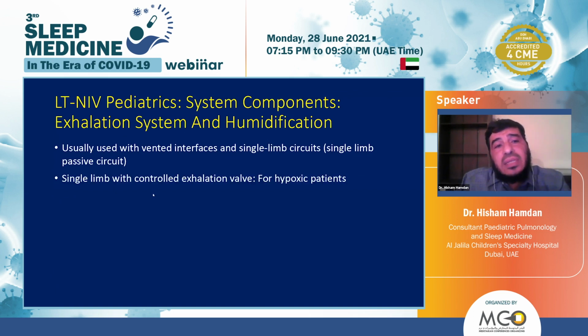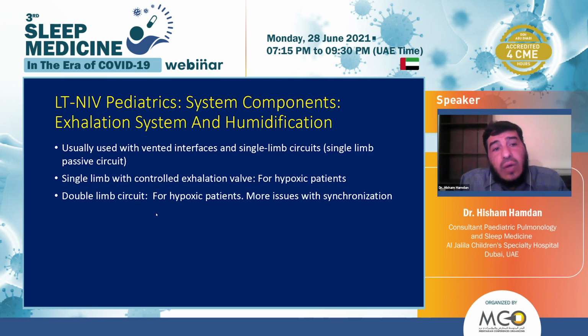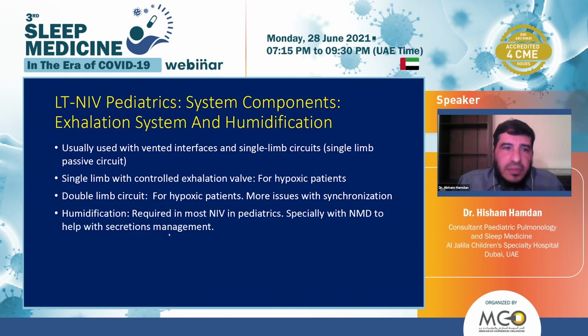The second option is single limb with controlled exhalation valve. So you have one limb, meaning one tube going from the ventilator to the mask, but then you have an exhalation valve that is actively controlled by the ventilator mechanism. And then you have the double limb circuit, which is the most advanced, in which you can control inspiration and expiration. You can see two pipes from the vent to the interface. However, you can run into issues with synchronization with double limb circuits. However, they're good for hypoxic patients because they maintain a higher FiO2 than passive circuits.